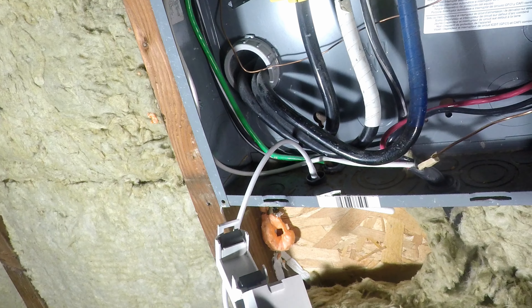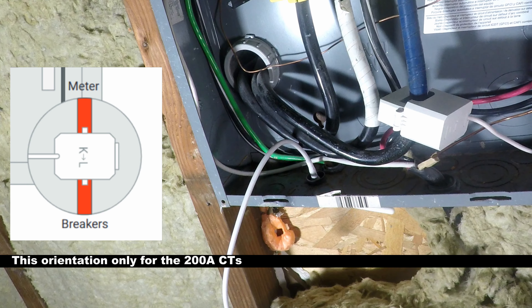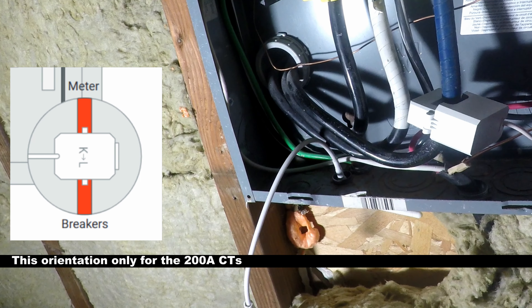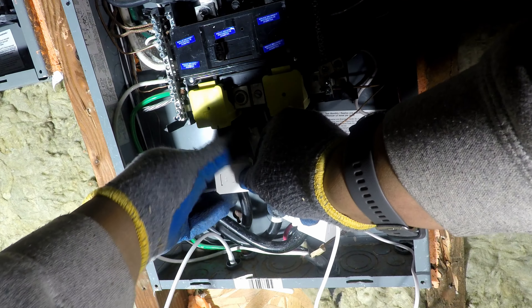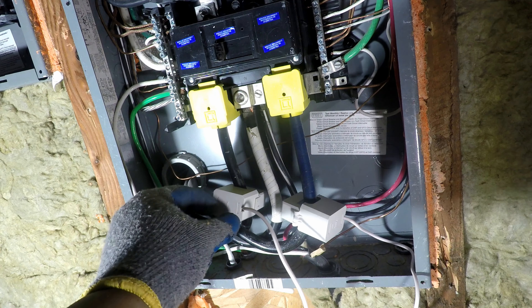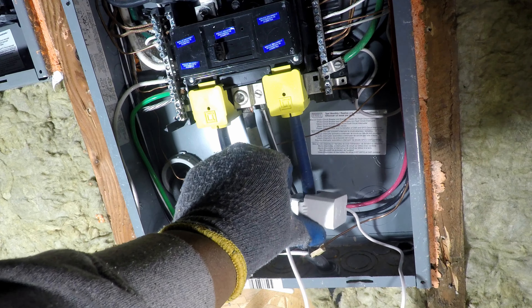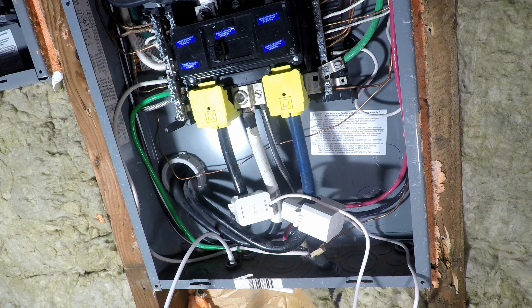The antenna will be hidden behind the insulation and drywall. This is a current transformer, or CT. The CT needs to be placed around one of the main service cables. At the bottom of the CT is an arrow — when placed around the service main cable, following the cable in the direction of the arrow should lead to the breaker. It can be said the K represents the meter and L represents the breaker: from the meter to the breaker. The second CT is installed on the black service entrance cable, taking care to ensure the orientation of the arrow is correct.